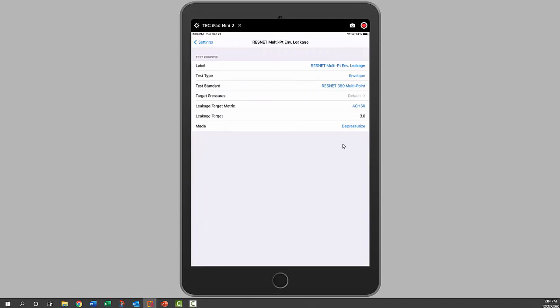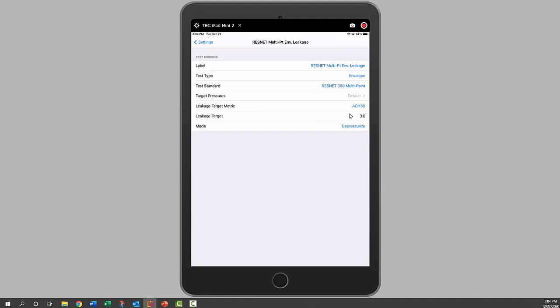We can choose between pressurize and depressurize. If you want a leakage metric and a target to show up in the report, you can show these, otherwise you could choose none. In this case we chose air changes per hour and three. Then in the bold in the center of the report it will show that the target is three air changes per hour and what your results were from the test, maybe 2.5 air changes per hour, and that it passes. So that information for the building official will be there.